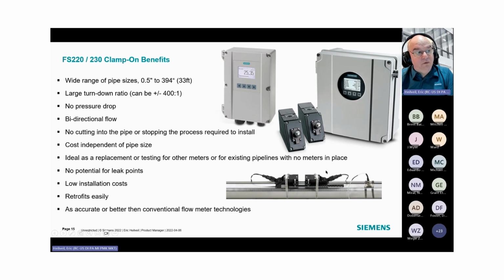So that kind of adds to the benefits because these cables are costly. So if you had a 4-path system in a Class 1 Division 1 area, then you could be spending thousands and thousands of dollars on cables that are just 10 meters long, or 30 feet. But with the SSL cable, it's pennies a foot. So you choose short cables at the install site and then run the digital cable out to the transmitter. And the added benefit to the cost is signal degradation. It's a digital signal on a Modbus line, and instead of an analog signal running through high resistance coax cable, you're running on an SSL cable. So if you have external noise, you have a VFD or a pump or something, the digital signal is not disrupted or affected by that. So that is an awesome question.